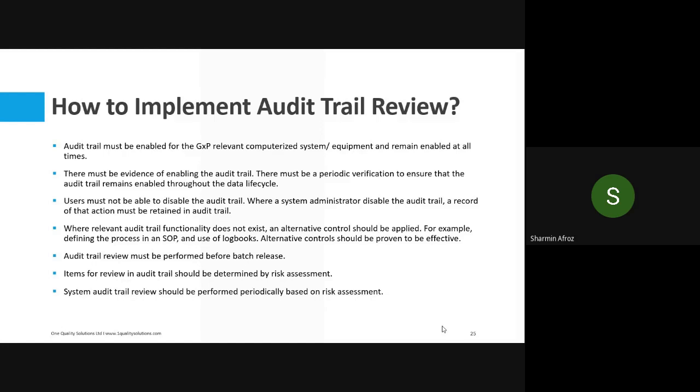Audit trails subject to regular review should include, but are not limited to, the change history of finished product test results, like changes to sample information, identification, changes to critical process parameters, etc. The audit trail would operate silently, recording who did what and when. The only user option would be to configure the audit trail to have a reason for change.